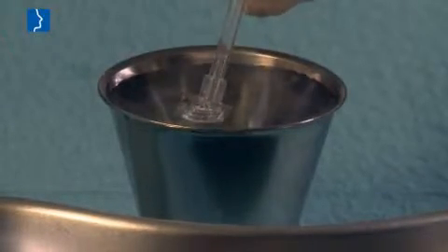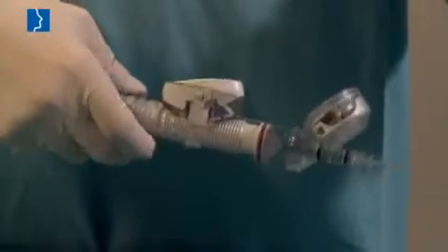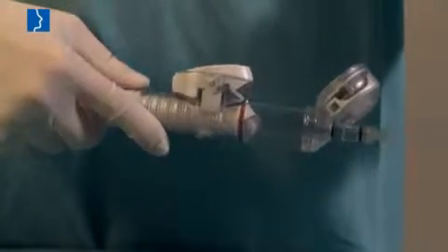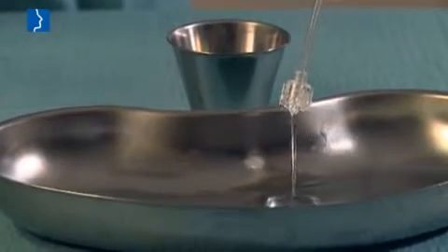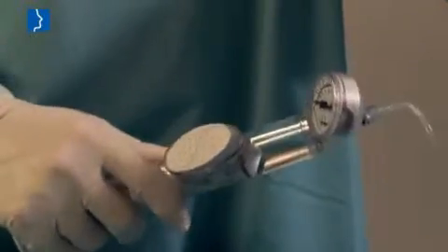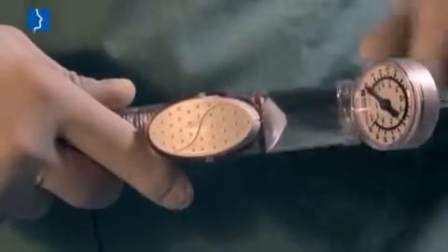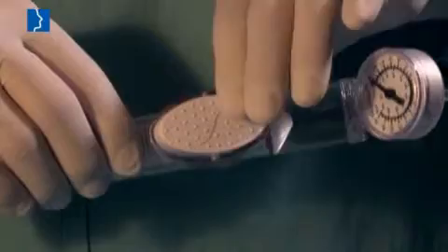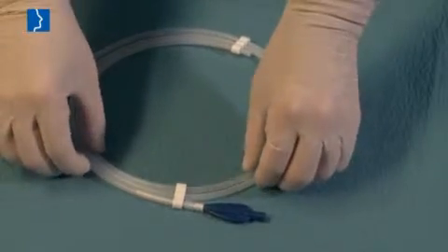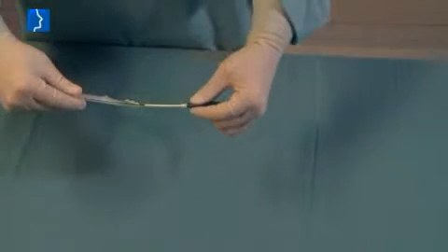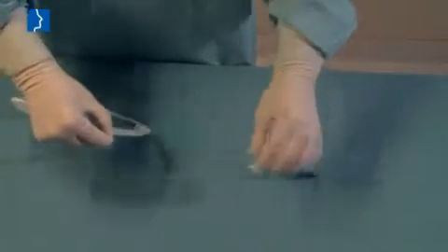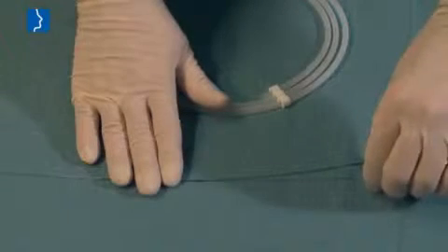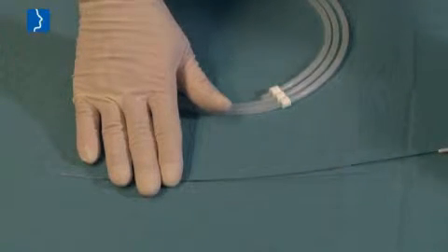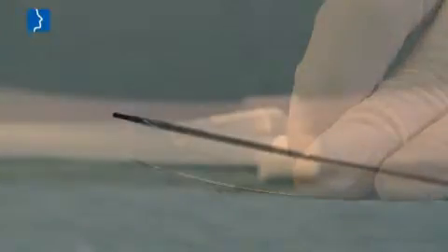Aspirate a sufficient amount of physiological saline solution into the piston of the inflation pump. Make sure that the pump's reservoir contains virtually no air bubbles. Lock the pump using the switch. Carefully remove the balloon catheter from its protective tube. Remove the stabilizing wire and the protective cap from the distal catheter part.